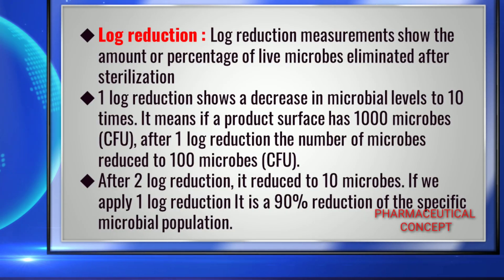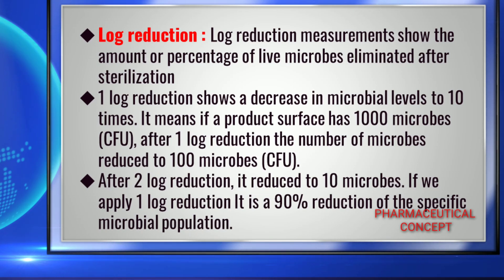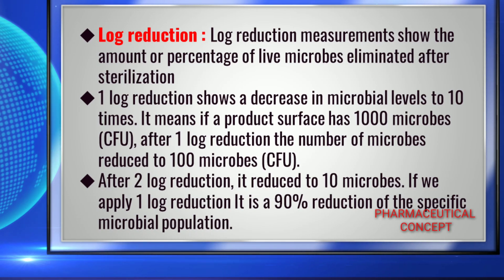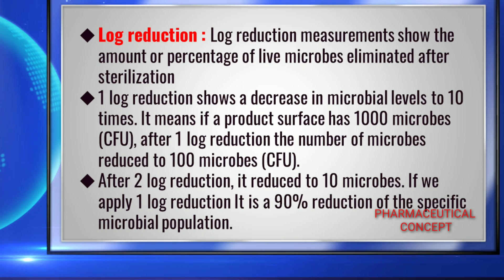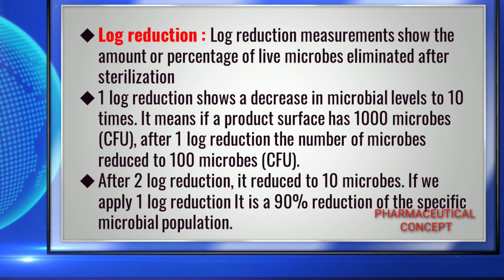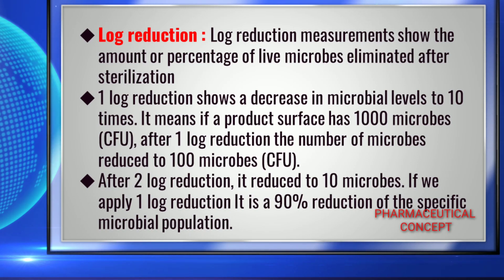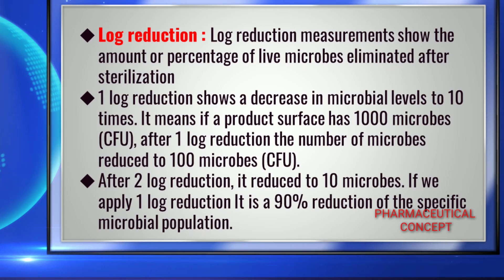Log reduction measurement shows the amount or percentage of live organisms eliminated after sterilization. One log reduction shows a decrease in microbial levels of 10 times. If a product surface has 1000 microbes (CFU — colony forming units), after one log reduction the number reduces to 100 CFU, and after two log reductions it is reduced to 10 microbes. One log reduction equals a 90% reduction of the microbial population.